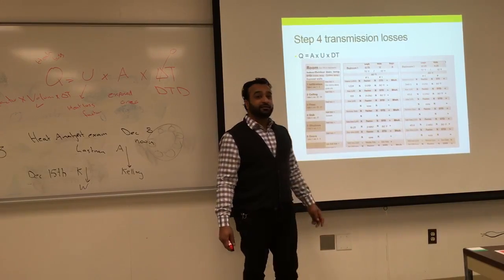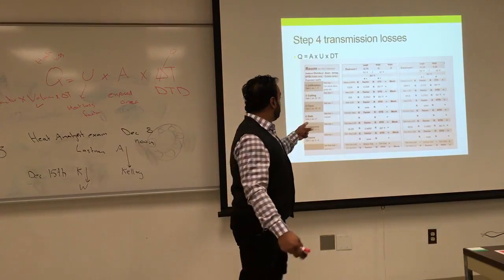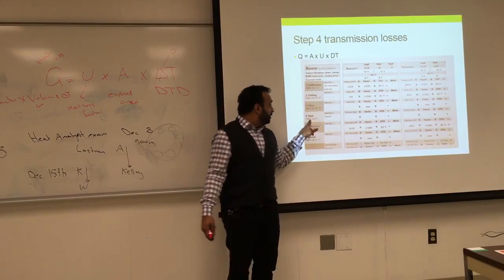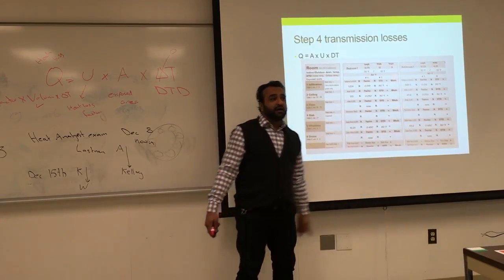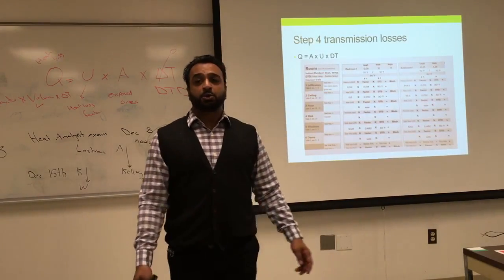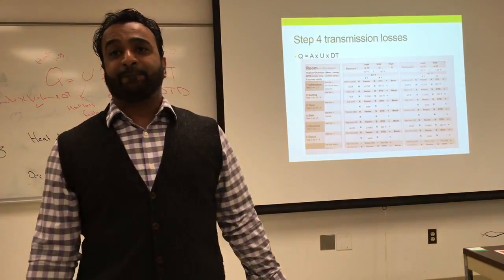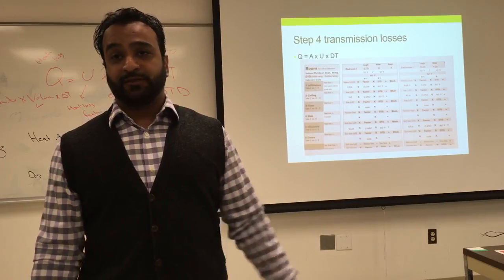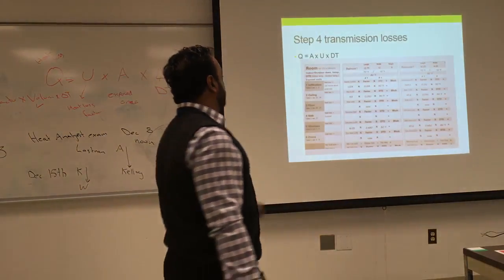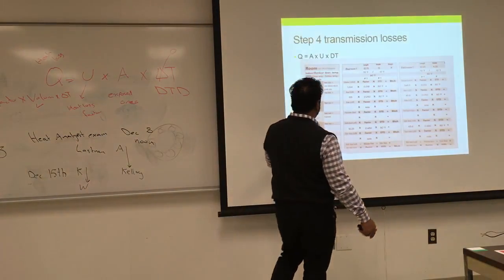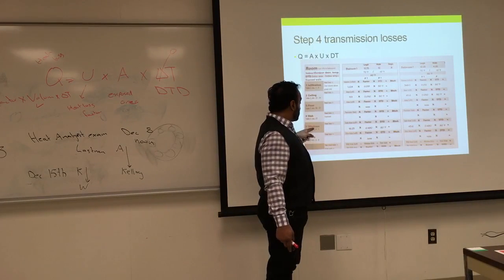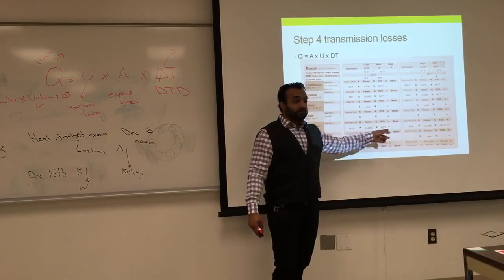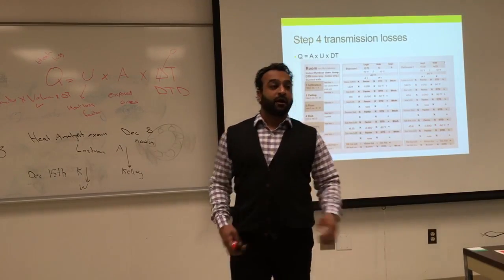And the factor, you find out from the book as well for slab and the floors. And they even tell you the table in the section where you find the slab. We get the factor, and that will be the heat loss if you have slab. Usually you'll have that in the basement. It's going to be slab, and if you're going to heat it, you probably have to consider that. Windows and doors, we know the tables, table 3, section 4 to 9, and here are the factors.